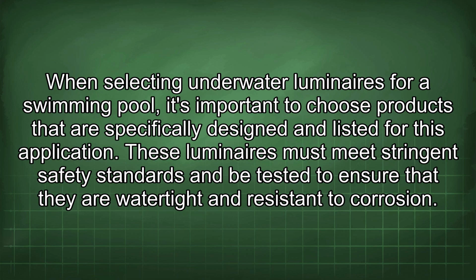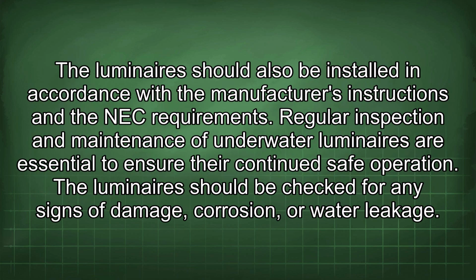this application. These luminaires must meet stringent safety standards and be tested to ensure that they are watertight and resistant to corrosion. The luminaires should also be installed in accordance with the manufacturer's instructions and the NEC requirements. Regular inspection and maintenance of underwater luminaires are essential to ensure the continued safe operation.